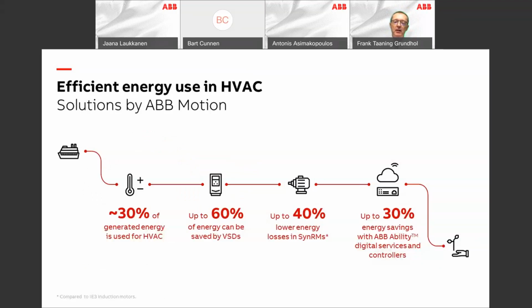So when we look at this 30% and the simpler options we have, the first and most significant saving really comes from applying variable speed drives. Variable speed drives applied to pumps and fans can save up to 60% of energy by running motors at the speeds required to produce the air or water flows needed in the system, compared to using a valve or a damper - which is essentially the same as running the motor at full speed and throttling with the valve. It's like putting the brakes on while keeping full speed on your engine in a car. Nobody drives a car like that, so why should our pumps and fans be run like that? Let's try and leverage that energy.